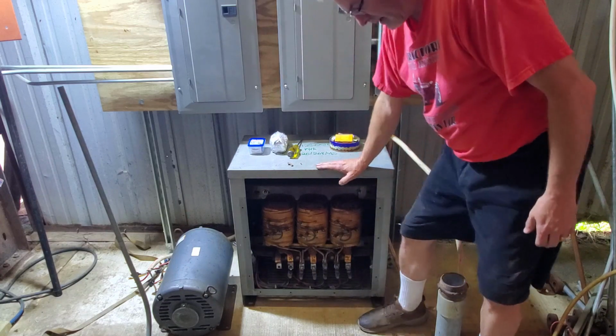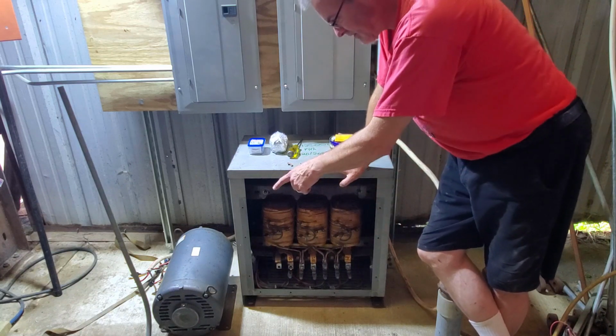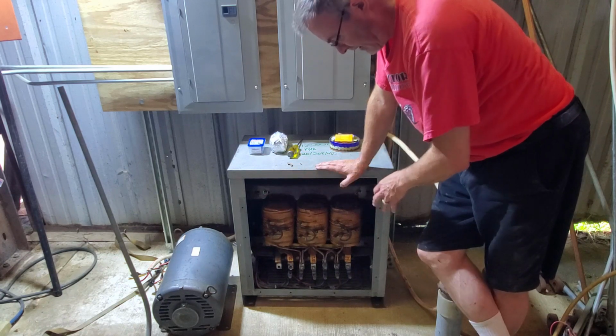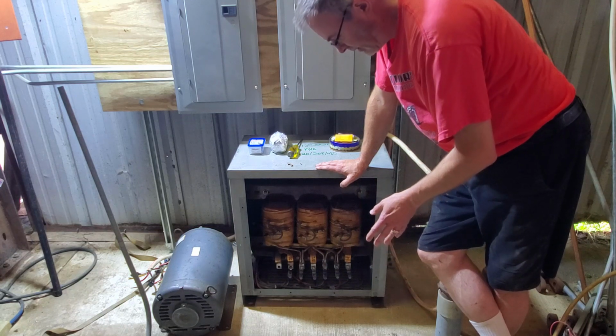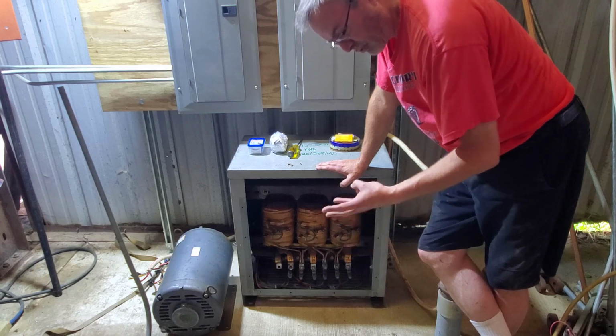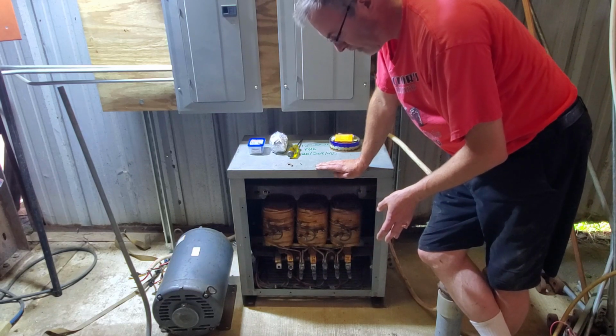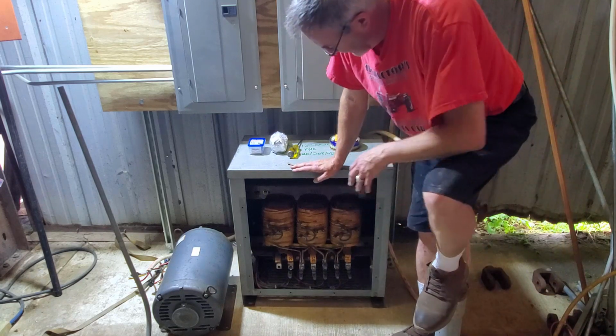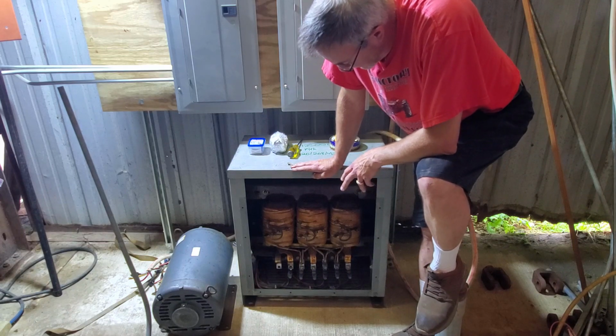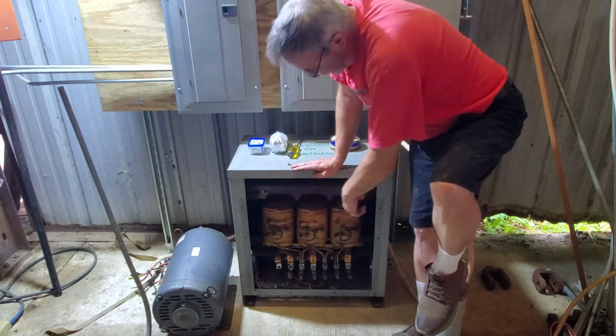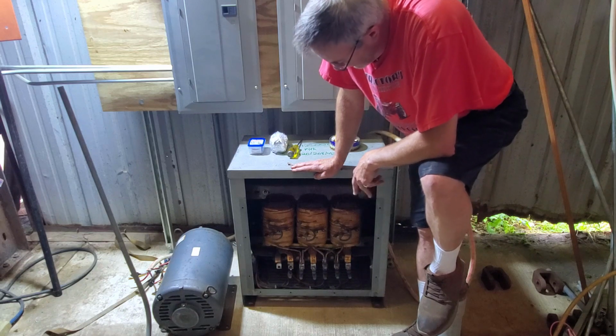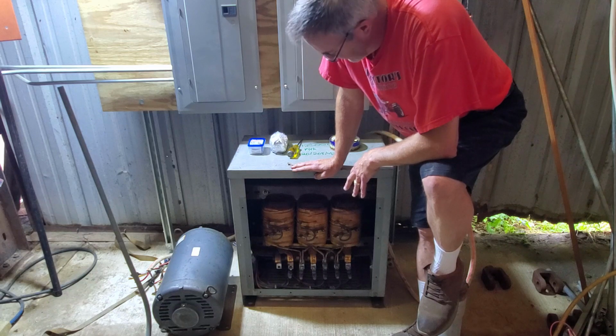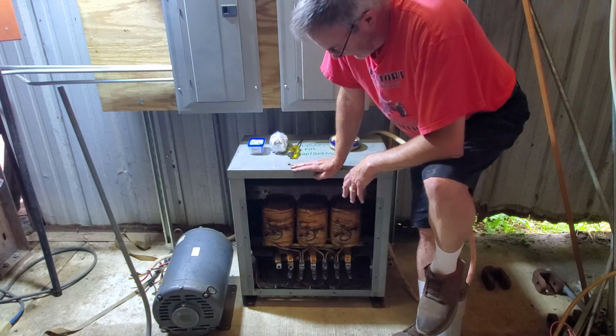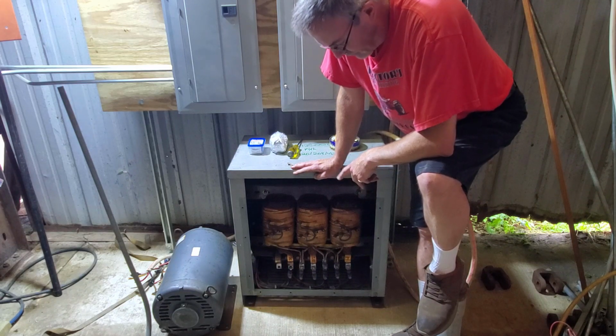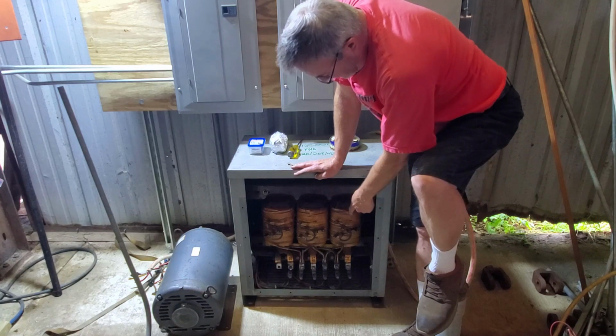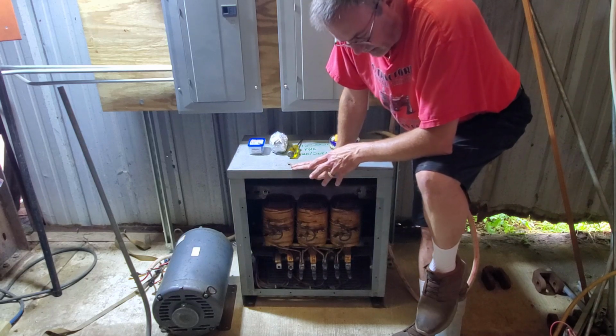I'm going to try something I've not seen done with a phase converter, which is to run the phase converter through the transformer wired for high voltage. I have a few motors, including the Monarch lathe motor, which are wound for high voltage only, with only 3 wires coming out, so you can't reconfigure them to run 220 or 208 3-phase. So I'm going to experiment with this, feeding it from single phase 220. Because there are multiple taps and jumper settings on the high voltage windings, I think I can get this thing to step up to a correct 460 volts just by playing with the jumpers. Then the starting capacitors for the phase converter will feed the ghost leg, get stepped up in voltage, and we'll start the motor on high voltage.